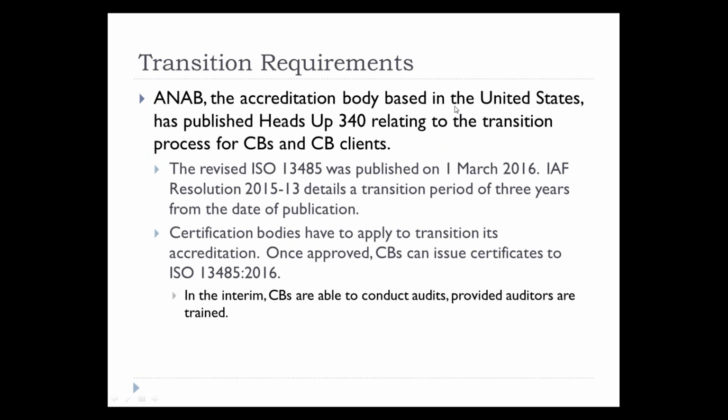So first, let's talk about the transition requirements. ANAB, the accreditation body, which is based in the United States, has published Heads Up 340, and anyone can access that through the ANAB website. This heads up relates to the transition process for both CBs and clients of certification bodies. The revised ISO 13485 was published on the 1st of March 2016, and IAF Resolution 2015-13 details a transition period of 3 years from the date of publication.